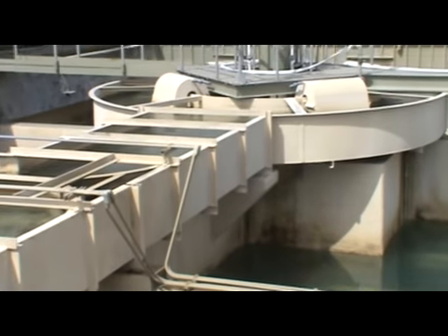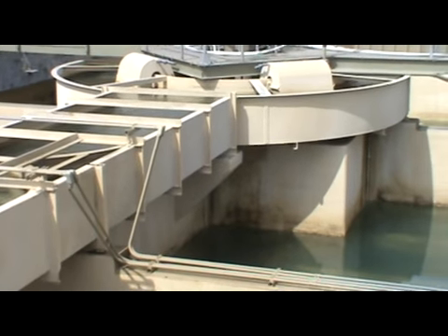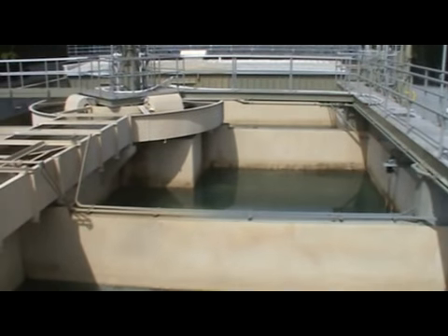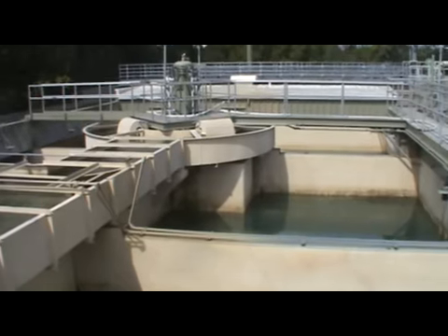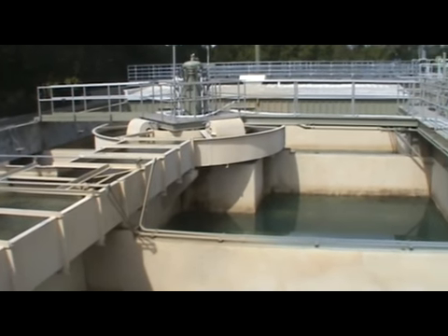Now, a lot of people think that's all filtration is: just pushing the water and the filter filters it out, a micro straining process. That is part of it, but that is far from the most important part of how filtration works. Basically, the biggest part of filtration on a filter bed like this is something called adsorption. If you remember when I was talking way back at the flash mix, I was saying that raw water in its natural state has no charge, but the particles in raw water have a slightly negative charge.